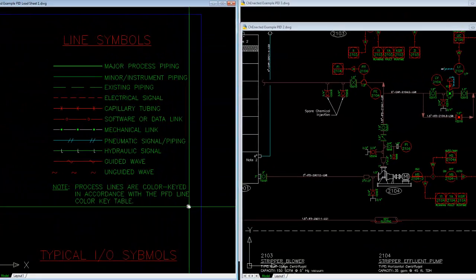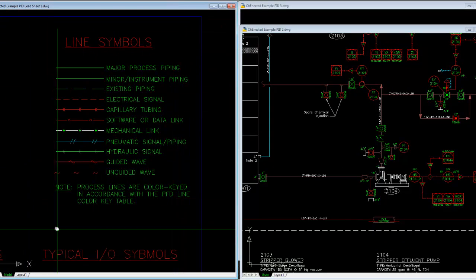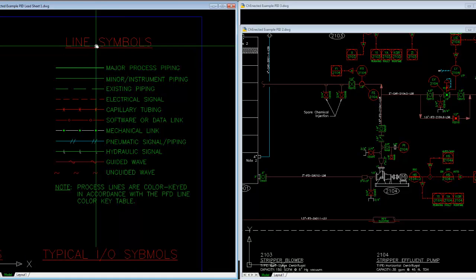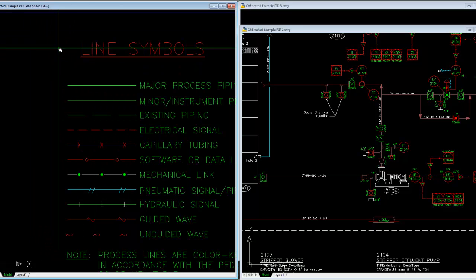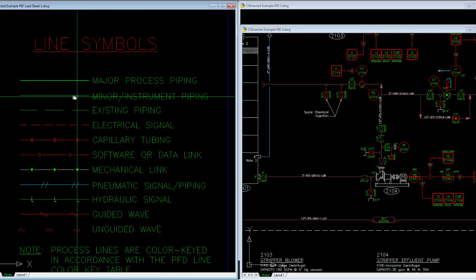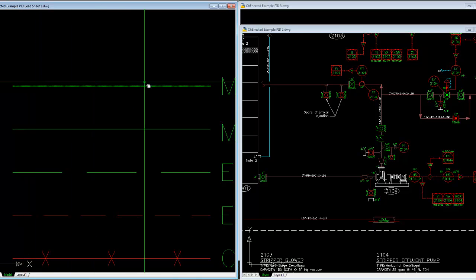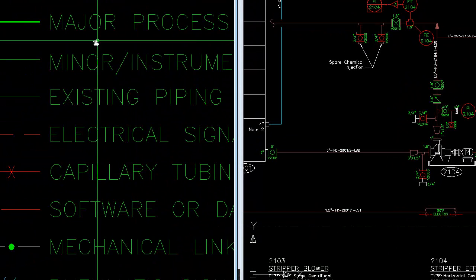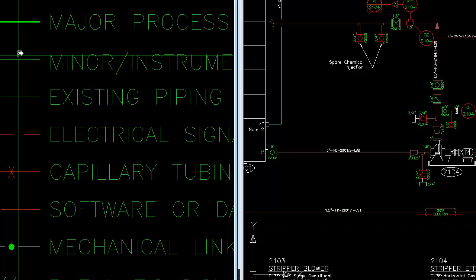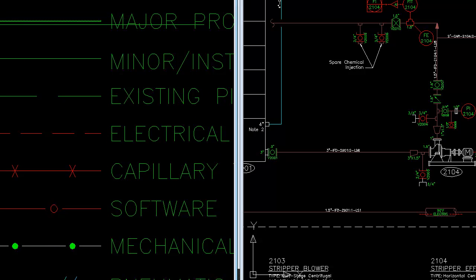Which are very self-evident and very much to the discretion of the company that's developing lead sheets. Some of these are nuances, the way I tend to draw P&IDs are all the process piping and instrumentation, even though I show it here, is somewhat thicker for so-called major process lines than minor. It comes down to what's major and what's minor, does it really matter? Can a person really see that one line on a P&ID is thicker than another, especially when they're being copied and distributed multiple times over, and the nuances of a major and minor line, unless the thickness is really exaggerated, become lost in the ability of the printer or copier to resolve that, or folks to see it.